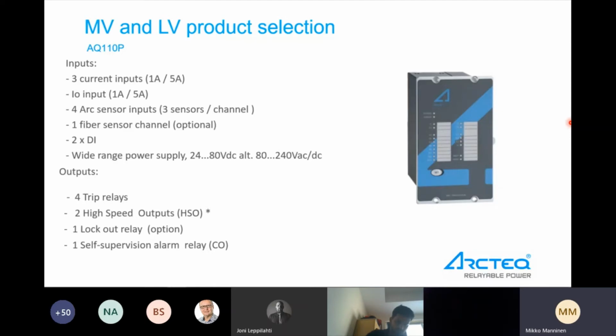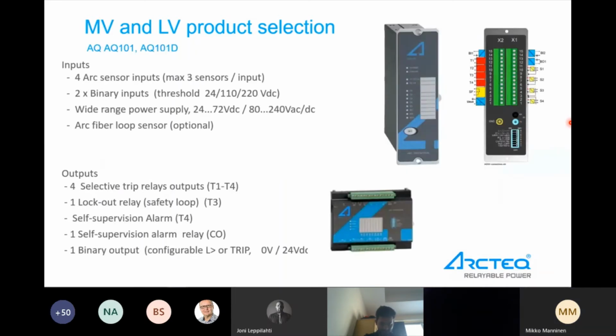And the power supplies, high-speed outputs, and lockout relay as an option. So a trip output 3 is a lockout relay. And then every unit has this self-supervision alarm. (101) and 101D, 4 arc sensor inputs. So altogether 12 sensors, 2 binary inputs. Thresholds can be selected from 24, 110, and 220. And this has to be selected when ordering the device, because it is a hardware change.